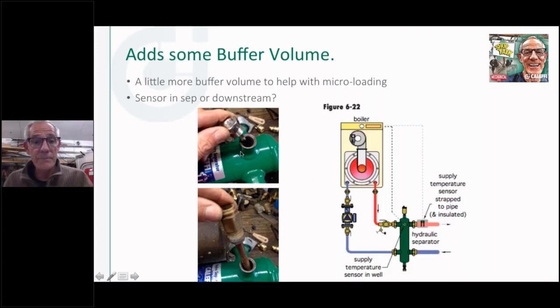We do make a couple different ways you can put a sensor in there, and the well that we make takes the small diameter sensors that most boilers are coming with these days, 6mm, about a 1/4 inch diameter. You can put your own well in there. That is a BSP straight thread, so you really should use a BSP fitting. You can, with a little bit of Teflon tape on this, make it work.